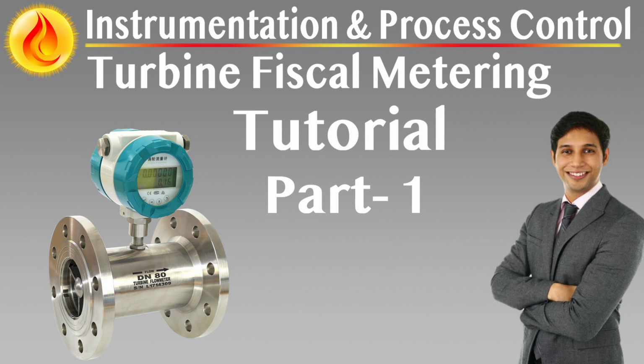Turbine meter assembly and signal redundancy. Each turbine meter is equipped with dual magnetic pickups and preamplifiers to enable pulse verification, fault detection, and redundancy. The design must support real-time pulse comparison for integrity checks and allow pickup replacement without meter removal. This supports SIL-level voting logic and ensures signal continuity during diagnostics or field servicing.